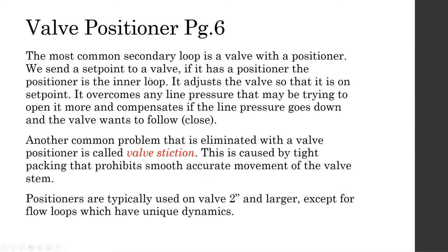So what the positioner does, it adjusts that valve so it's always on set point, as opposed to an I to P, which we would never know. It will overcome any line pressure that might be trying to open it more and compensate if the line pressure goes down and the valve wants to follow it. It basically just looks after the valve.